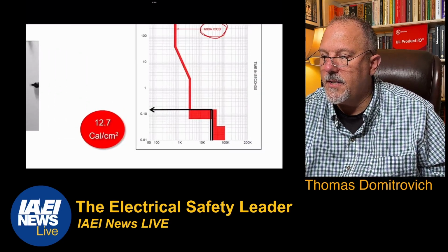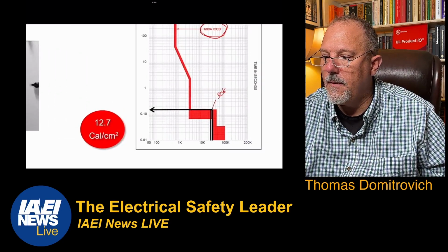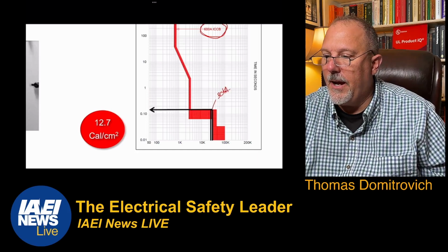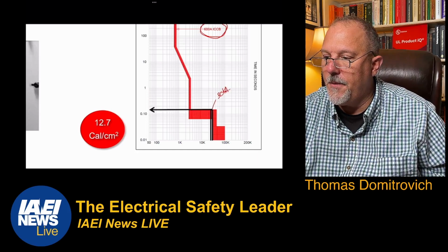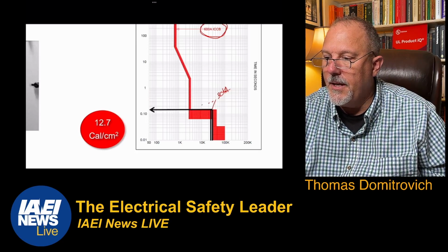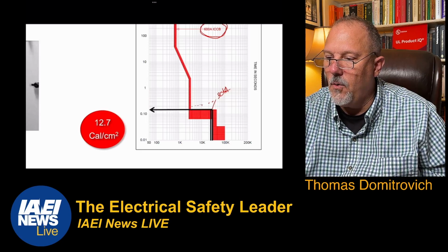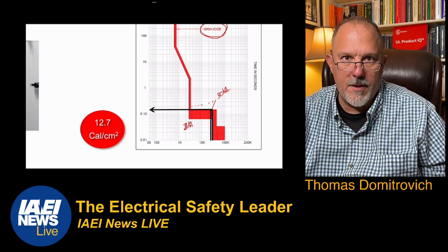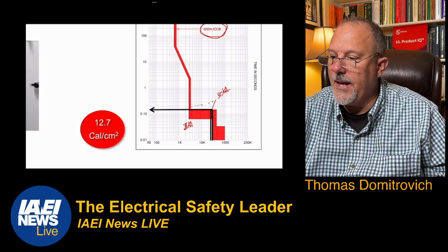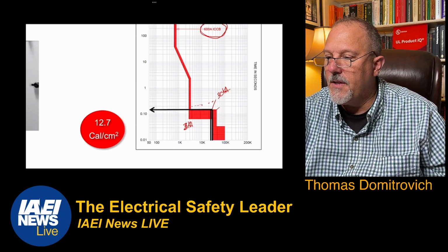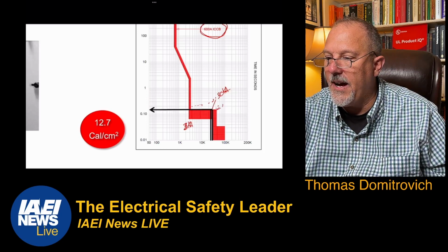10, 20. So this is still 30K, right? And 30, 29, 28. That's 10,000, 10, 20, 30. This is 10,000, 9, 8, 7, 6, 5, 4. This is 3,000. So this picks up just around 3,000 amps. Remember the other one was around 1,600. 3,000 amps through, this is 30, 40, and this is 50, so about 45 kA.